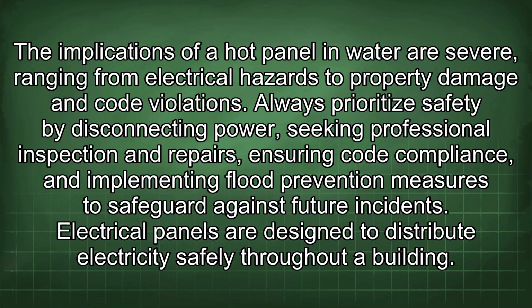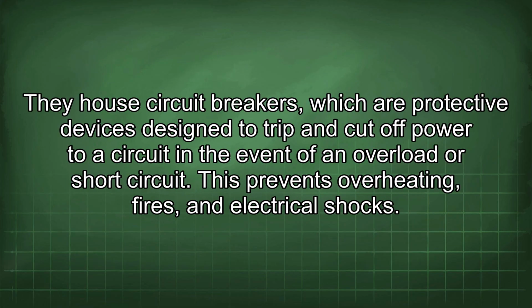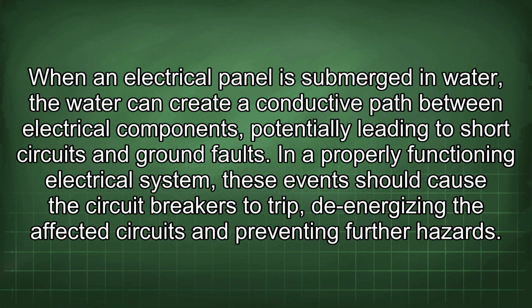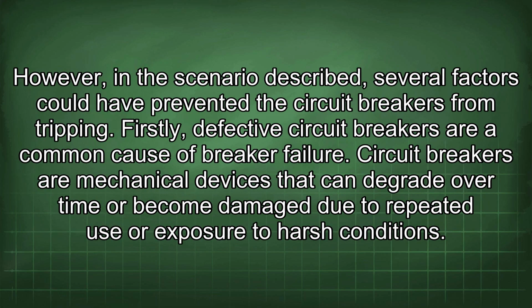safeguard against future incidents. Electrical panels are designed to distribute electricity safely throughout a building. They house circuit breakers, which are protective devices designed to trip and cut off power to a circuit in the event of an overload or short circuit. This prevents overheating, fires, and electrical shocks. When an electrical panel is submerged in water, the water can create a conductive path between electrical components, potentially leading to short circuits and ground faults. In a properly functioning electrical system, these events should cause the circuit breakers to trip, de-energizing the affected circuits and preventing further hazards. However, in the scenario described, several factors could have prevented the circuit breakers from tripping.